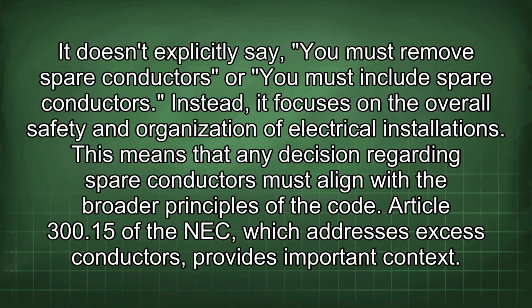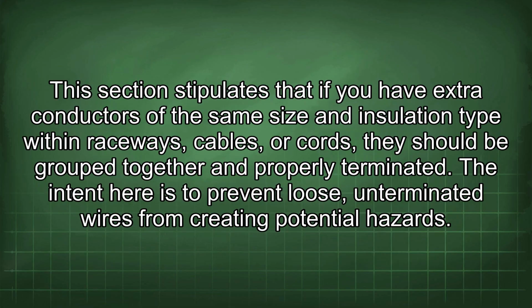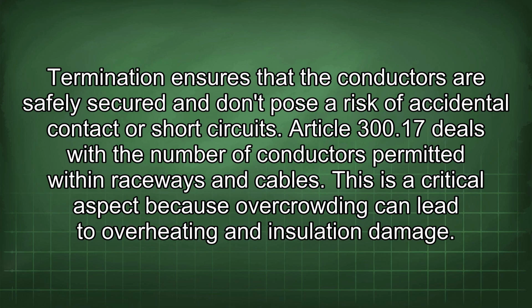It doesn't explicitly say you must remove spare conductors or you must include spare conductors. Instead, it focuses on the overall safety and organization of electrical installations. This means that any decision regarding spare conductors must align with the broader principles of the code. Article 300.15 of the NEC, which addresses excess conductors, provides important context. This section stipulates that if you have extra conductors of the same size and insulation type within raceways, cables, or cords, they should be grouped together and properly terminated. The intent here is to prevent loose, unterminated wires from creating potential hazards. Termination ensures that the conductors are safely secured and don't pose a risk of accidental contact or short circuits.